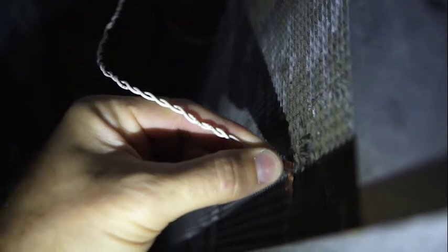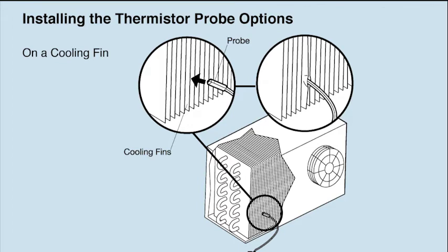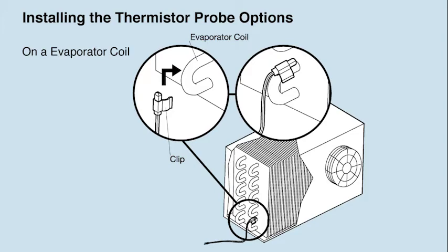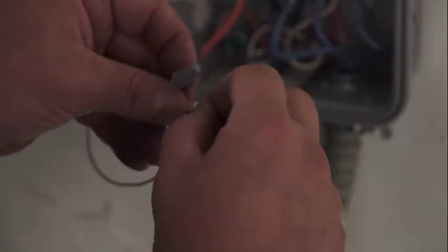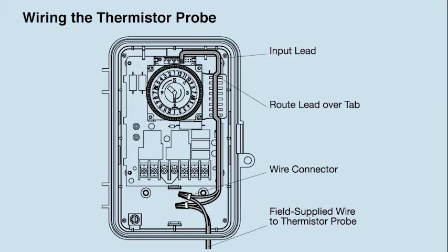Now, inside the freezer, position the thermistor probe and connect it to the evaporator coil. There are a few ways to connect the probe to the coil. You can insert the probe between the cooling fins, which is what we did for this installation. You may need to use needle nose pliers to carefully bend the cooling fins together so the probe stays in place. Or use the clip that came in the box to clip the probe onto one of the lower coils. Now, use the provided wire connectors to connect the thermistor probe wires to the input lead wires. And be sure to secure the wires as illustrated.